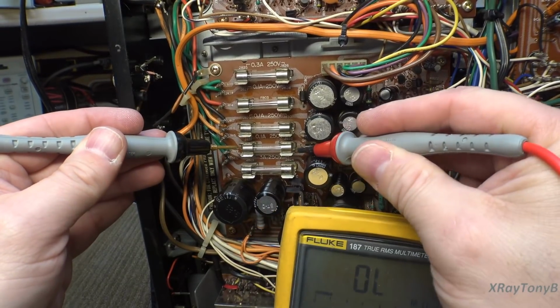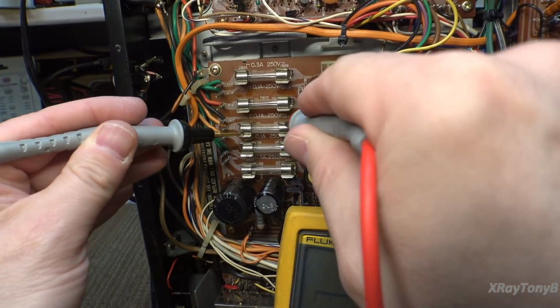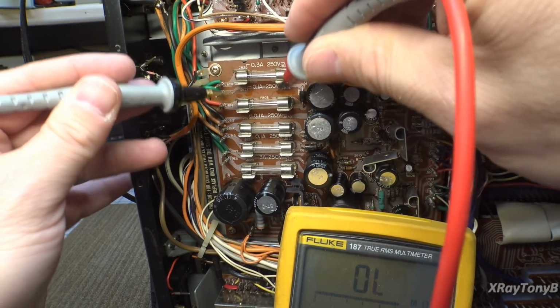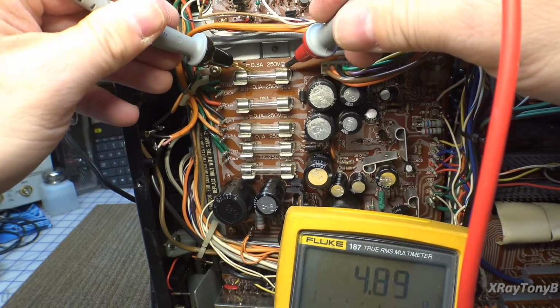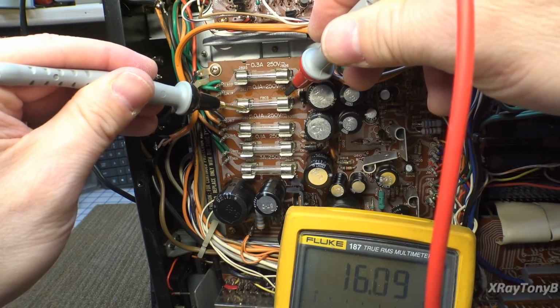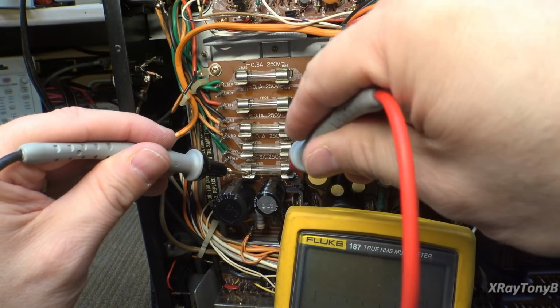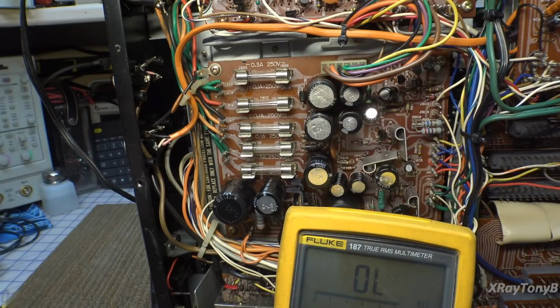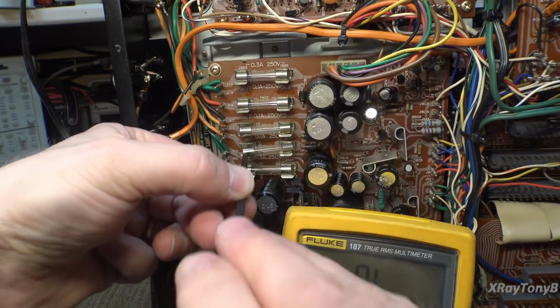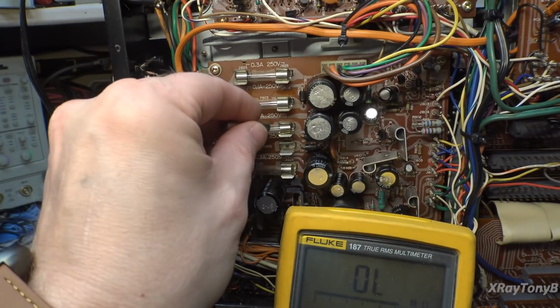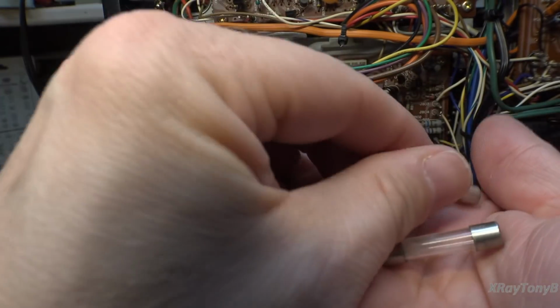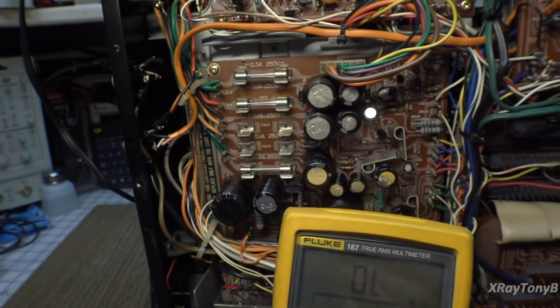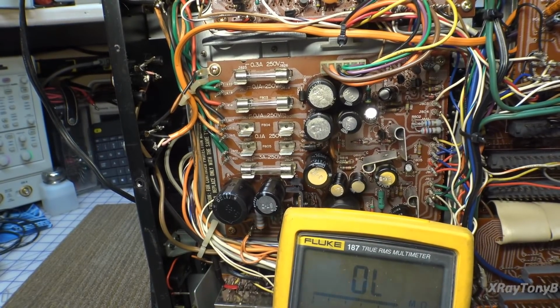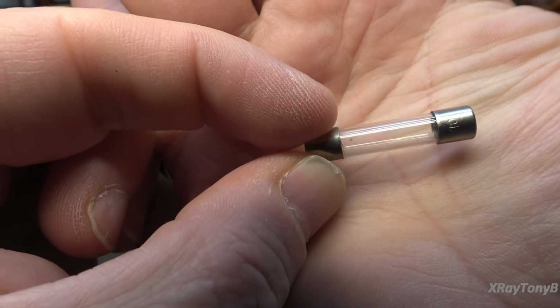This fuse, as well as this fuse, are both open. Now all the rest of them are good. You can see these are very low current fuses, so they're going to have some resistance on them, except for this 3 amp down here. But these two fuses are blown. If we pull them out, we can in fact see that they are bad, and you can just see the filaments are gone in them, the little center part—whoop, as I drop them on the floor. But you can see that they're just shot.